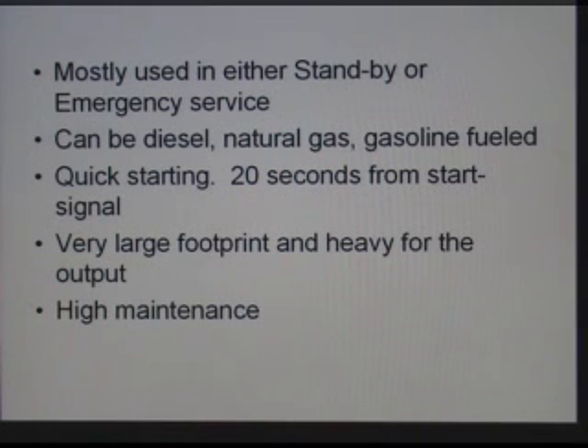So standby gen sets, they can either be diesel or natural gas or gasoline fueled. And they're generally very quick starting. 20 seconds from the time that you get a start signal until you're up online accepting load is not at all unusual, and generally 12 seconds is about the time frame that you're looking for. But they have very large footprints, and they're heavy for the output, and they're high maintenance. We talked about reciprocating engines a little bit last time, and this is just adding a generator to it, which doesn't improve its reliability at all.